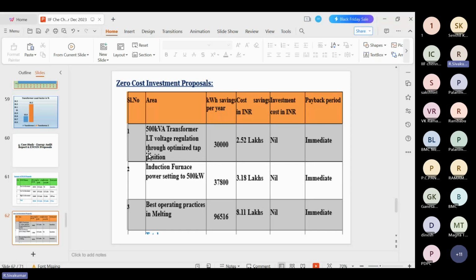Here are some zero cost investment proposals. For the 500 kVA transformer, LT voltage regulation by optimizing the tap position, since an OLTC is not available, around 30,000 units can be saved, and 2.52 lakhs rupees can be saved by this measure. And induction furnace power setting to 500 kilowatt, because currently the unit sets the power at only 430 to 450 units.